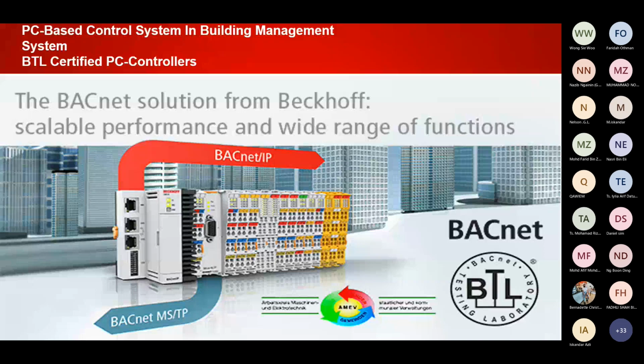Okay. While for the communication terminals, we can add the communication protocol that is required. For example, if the control system requires BACnet MSTP, we can just add it, and also Modbus RTU, LonWorks, DALI, CANopen, and also other protocols. So we can have multiple protocols in one control system. After all the hardware, we can look into the software. All the protocols commonly used in the BMS are already available in the library. So with the TwinCAT software, you can just call the function inside the library and communicate with the protocol required in the application system.